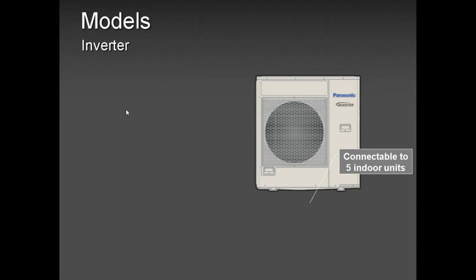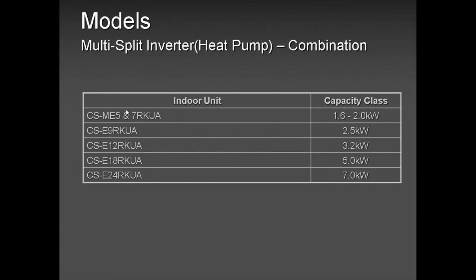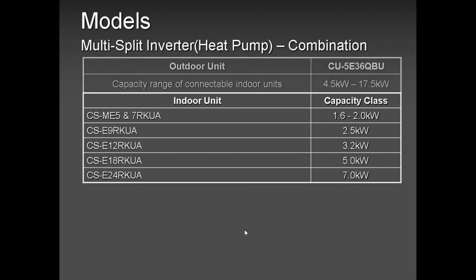Okay, let's continue with our multi-zone, and we are going to talk about the 5-zone. But truly speaking, multi-zone, 5-zone, 2-zone, 3-zone, and 4-zone are all the same. Not the same in capacity, but the same in operation. Unlike our single zone that can operate down to -15, multi-zone can operate down to -5, as you can see here in the model number. Okay.